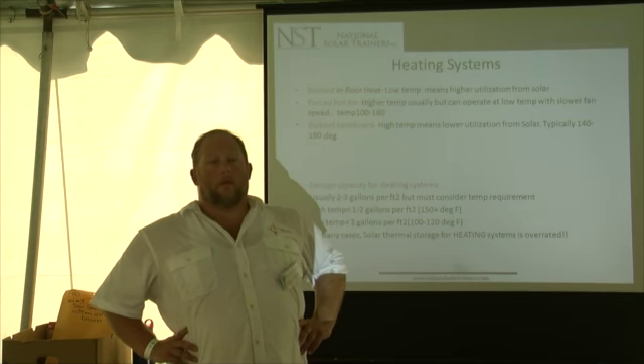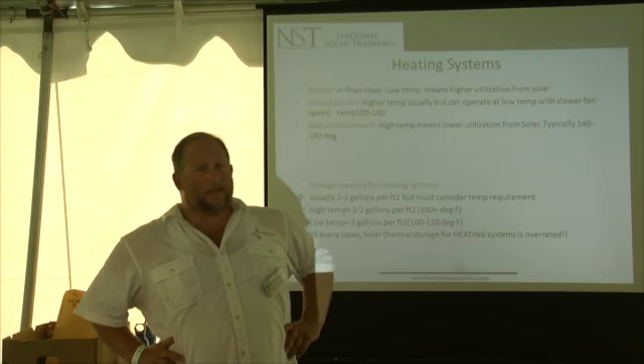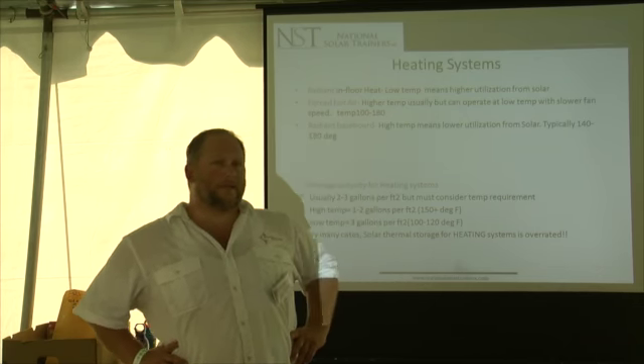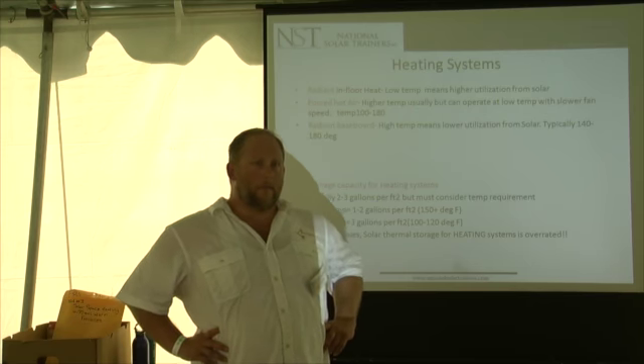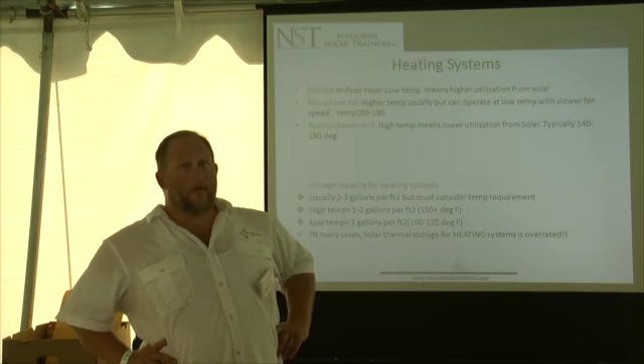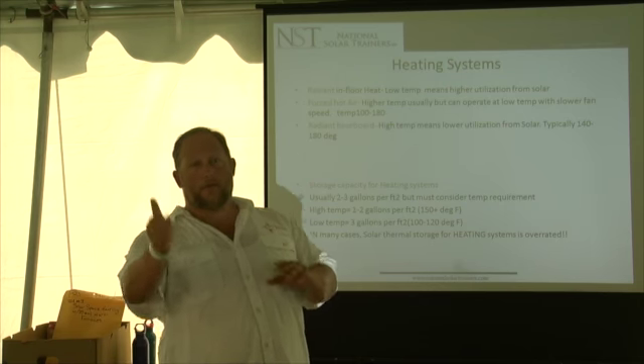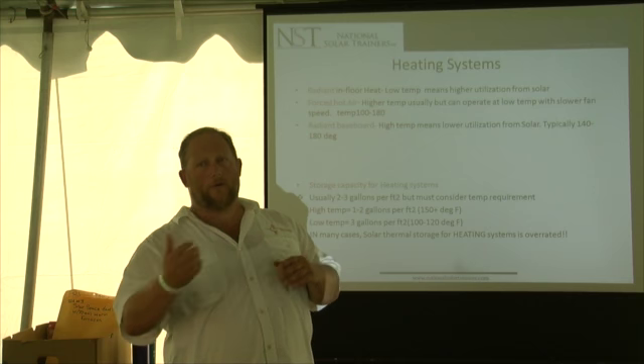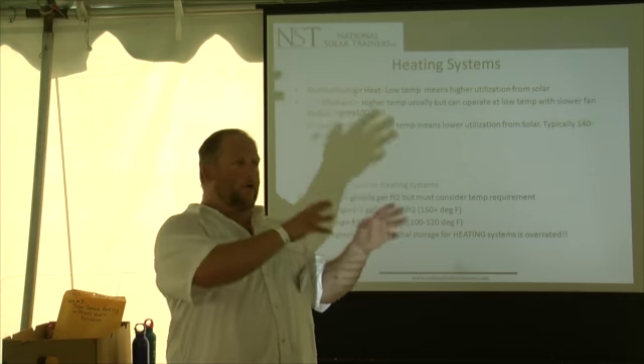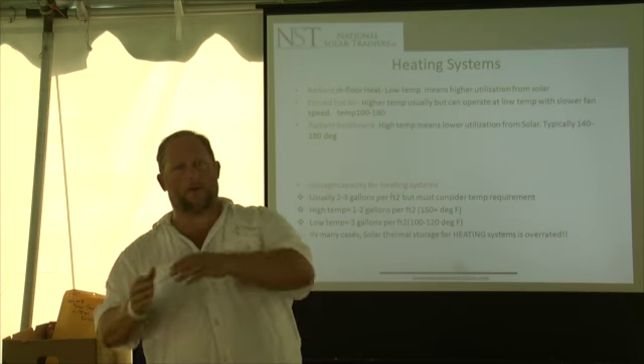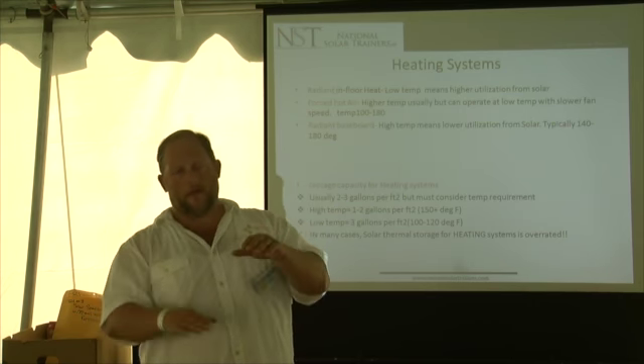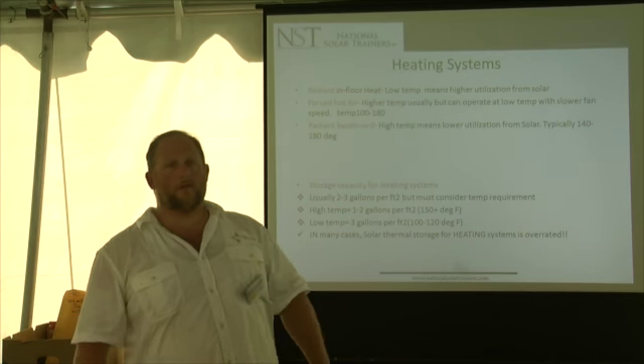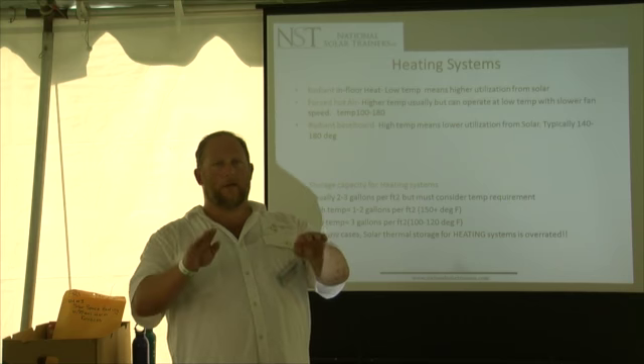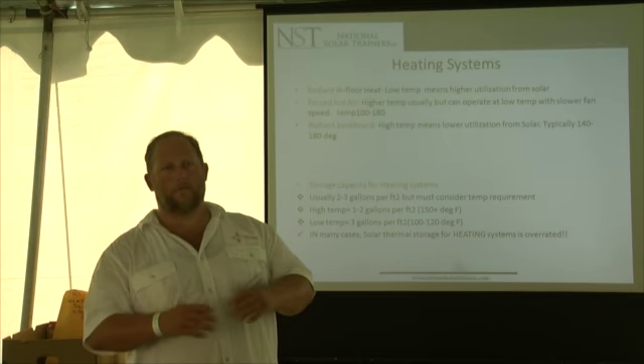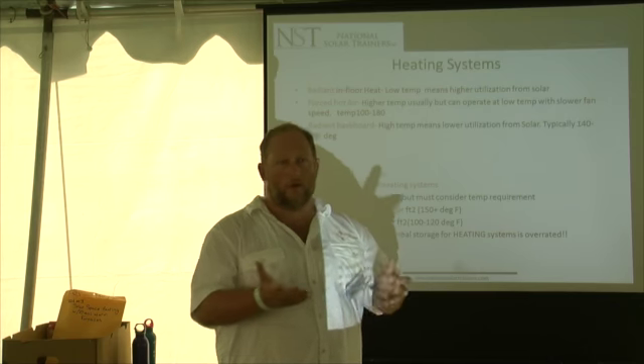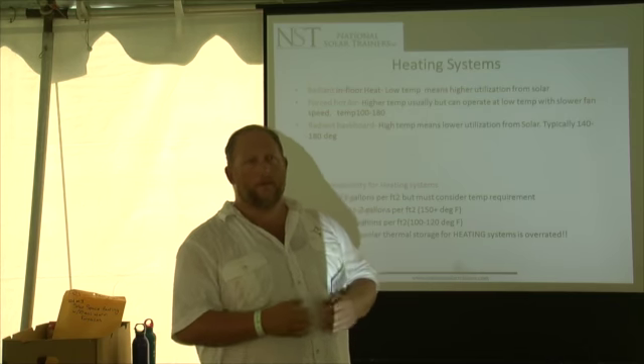So that you have warmer water going in. Yeah, you plumb it as the return to the boiler, which is generally about 17 degrees less than the supply. So that helps by plumbing it. Put your solar tank in series with the boiler, so that it goes from the boiler to the home, from the home to the solar to the boiler, and that allows you to bring that temperature set point down by no more than 17 degrees. That's the differential between your supply and return on the boiler. But that's one way you could improve it. Yeah.